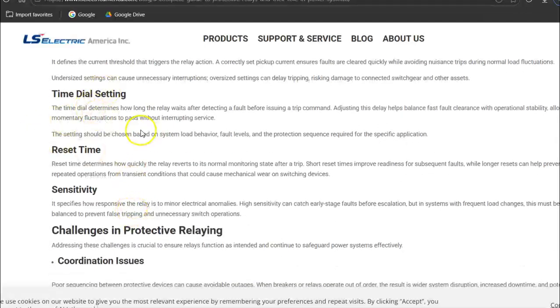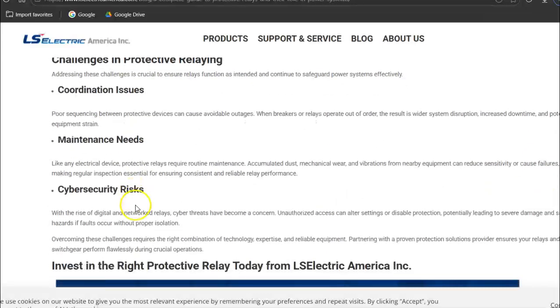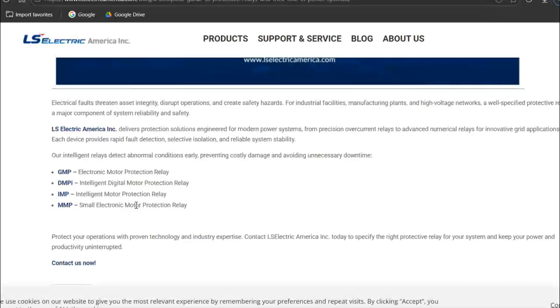They have settings like the delay. That's how fast it is before it actually trips. And this is how you'd coordinate with other ones. So the slowest ones are going to be at the substation. The fastest ones are going to be out in the field closer to the fault. Reset time is how long before it resets again. And then the sensitivity. High sensitivity can catch early stage faults before escalation, but in a system with frequent load changes, this has to be balanced because you'll get false tripping. So, protective relays. Very simple device really, but they're getting much more powerful all the time.